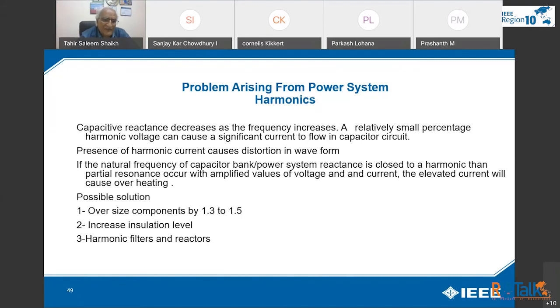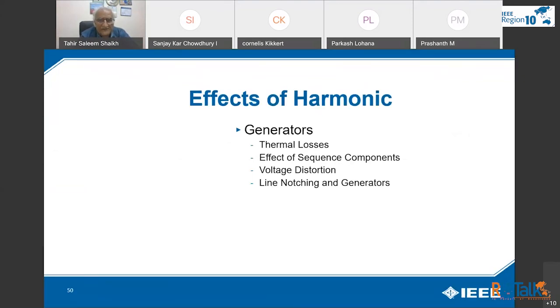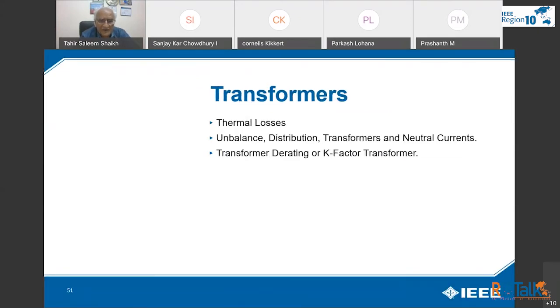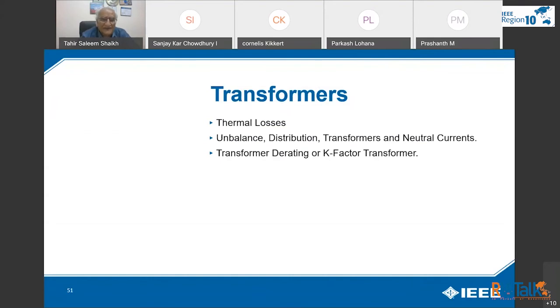Possible solutions: maybe one of the easiest is to oversize the component by 1.3 to 1.5, increase the insulation level, and third would be harmonic filters and reactors, which is a costly affair. In generators, if you are operating generators, there would be thermal losses, effect of sequence components, voltage distortion, and line notching. Transformers will have thermal losses, unbalanced distribution, and transformer neutral current. For selection of a transformer in an environment of harmonic distortion, you have to calculate the K factor. This is called transformer de-rating or K factor for transformer. If you are ordering a transformer for a harmonic environment, you can do this K factor calculation, find out what the K factor should be, and select your transformer accordingly.